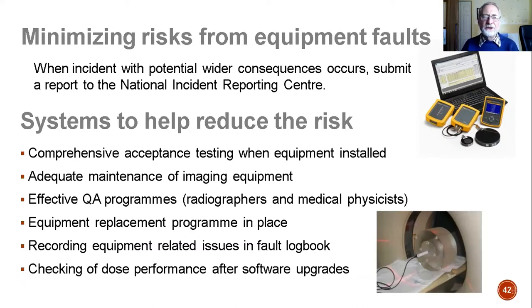It's useful to record equipment related issues in the fault logbook so that other users can see, and this also gives an indication of whether the equipment might need to be replaced. And then checking the dose performance after maintenance, after software upgrades, to make sure there's no changes being made that affect dose in ways people are not aware of.